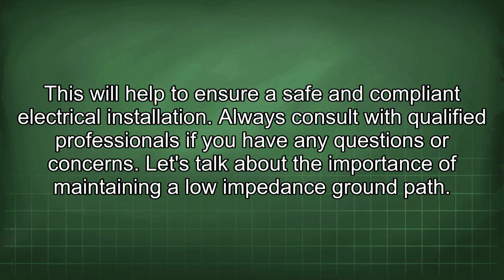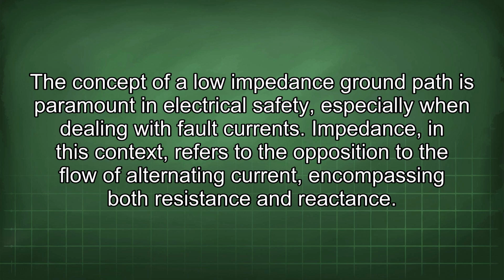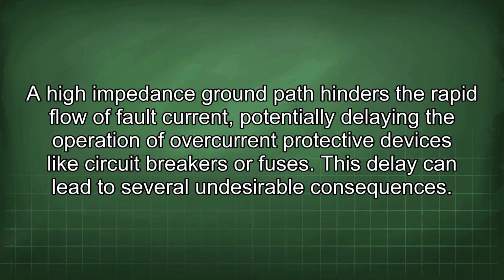Let's talk about the importance of maintaining a low-impedance ground path. The concept of a low-impedance ground path is paramount in electrical safety, especially when dealing with fault currents. Impedance, in this context, refers to the opposition to the flow of alternating current, encompassing both resistance and reactance. A high-impedance ground path hinders the rapid flow of fault current, potentially delaying the operation of overcurrent protective devices like circuit breakers or fuses. This delay can lead to several undesirable consequences.